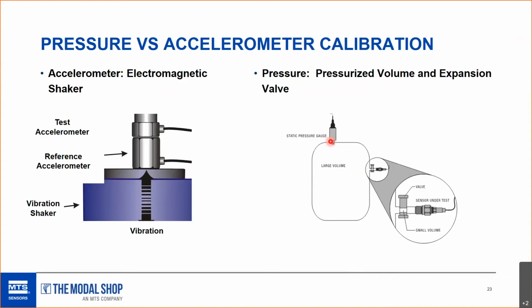And we expand that. We just open a valve into a very small volume over here on the right, where we have a sensor under test mounted. That causes a drop in measured pressure of the static gauge, but the drop is really, really low, below our ability to measure the difference. It's an incredibly small drop. And then we have a very controlled, very precise rise in pressure with a dynamic input to the sensor as we're measuring dynamic pressure events with it.